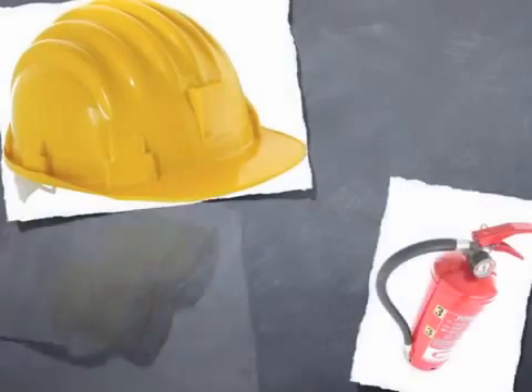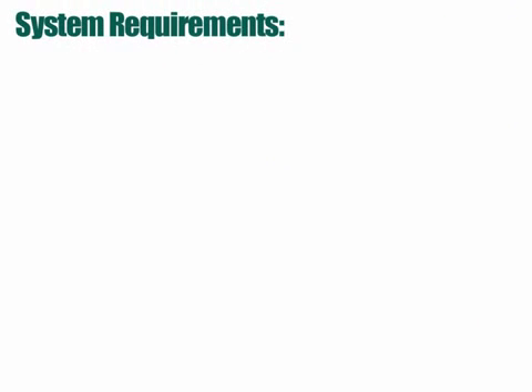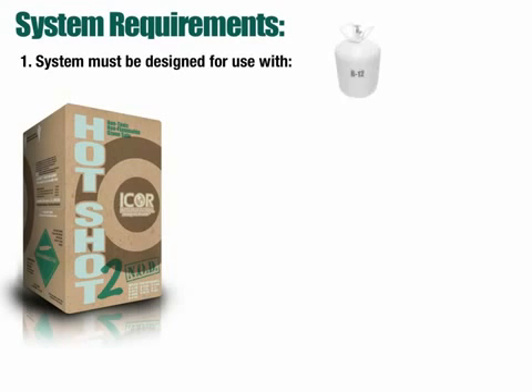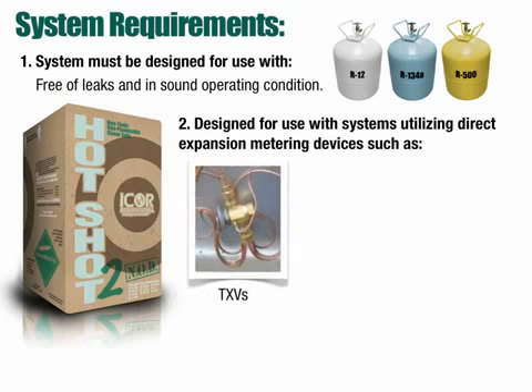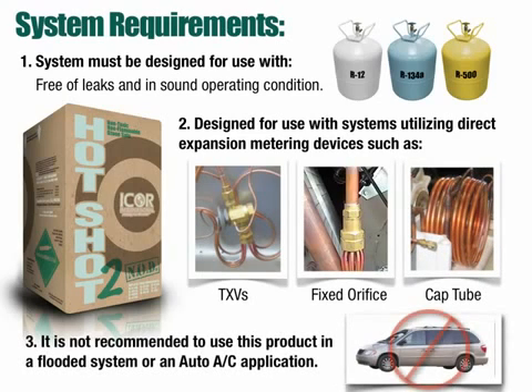It's always recommended to follow industry safety standards when servicing any air conditioning or refrigeration equipment. Failure to follow these standards could result in injury or equipment failure. ICOR recommends following these three requirements when considering retrofitting to Hotshot 2: 1) The system must be designed for use with R-12, R-134A, or R-500, free of leaks and in sound operating condition. 2) Hotshot 2 is designed for use in systems utilizing direct expansion metering devices such as TXVs, fixed orifice, or cap tube. 3) It is not recommended to use this product in a flooded system or an auto-AC application.